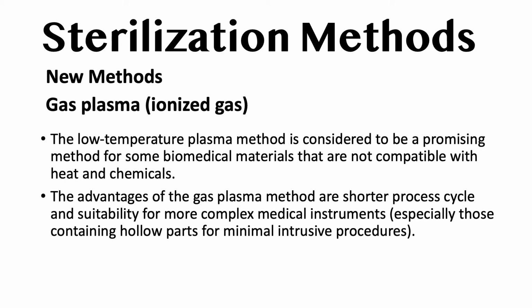Another new method is gas plasma, ionized gases. There are many types of gases that can be used. The low temperature plasma method is considered to be a promising method for some biomedical materials that are not compatible with heat and chemicals. The advantages of the gas plasma method are a shorter process cycle and suitability for more complex medical instruments, especially those containing hollow parts, for minimally invasive procedures.